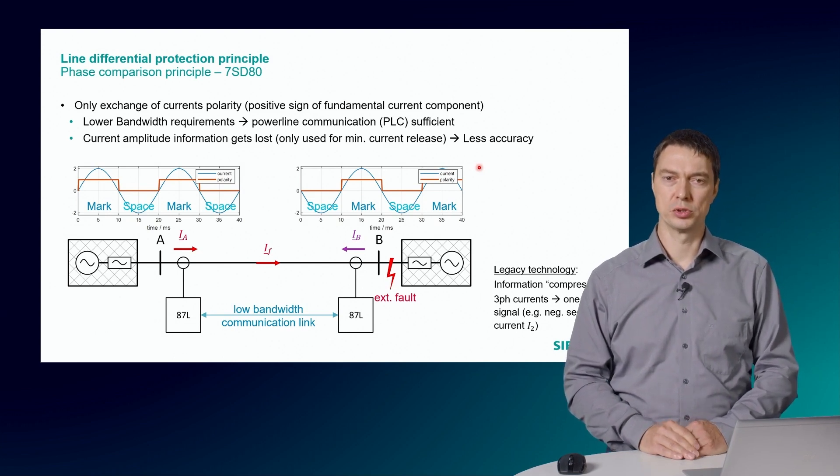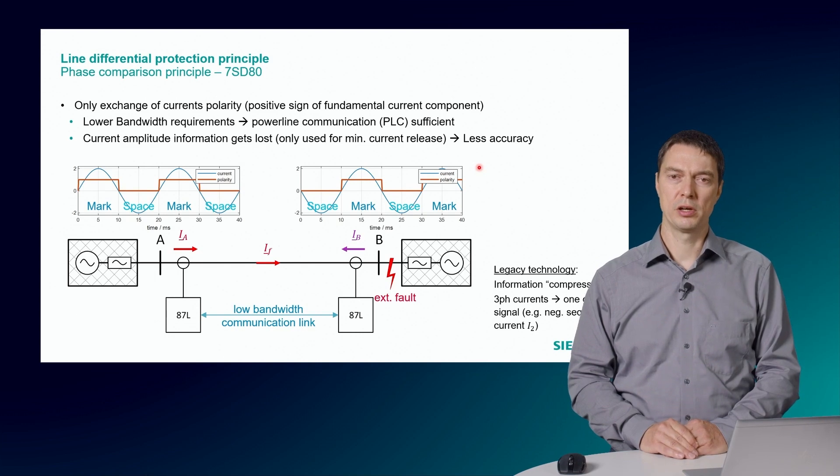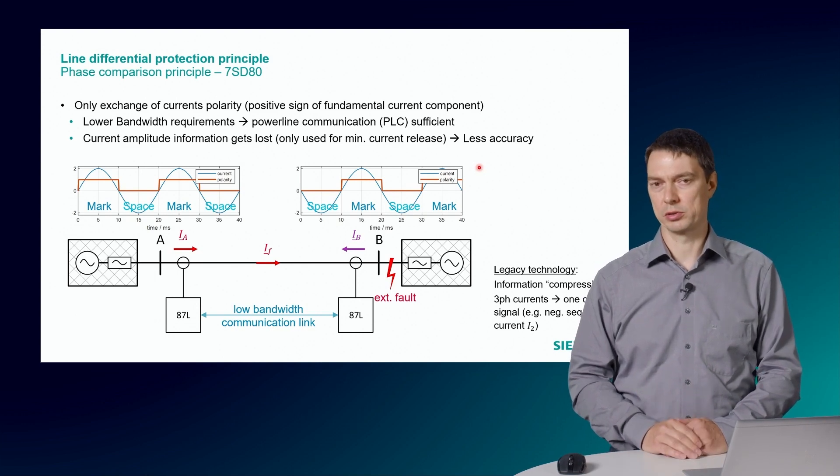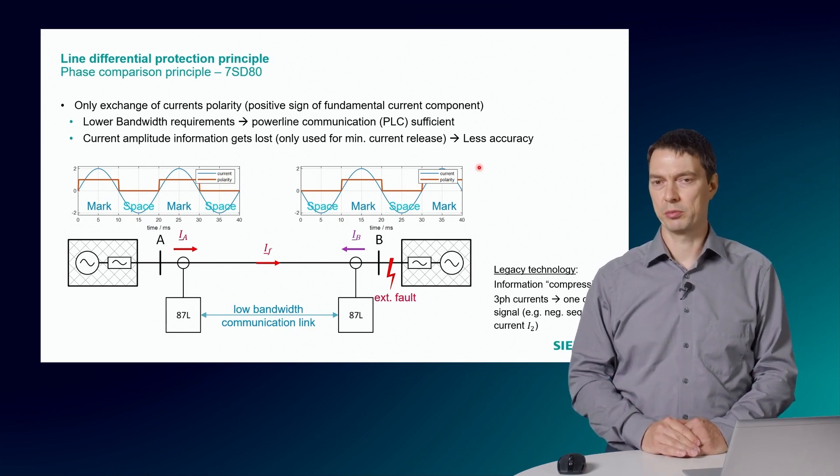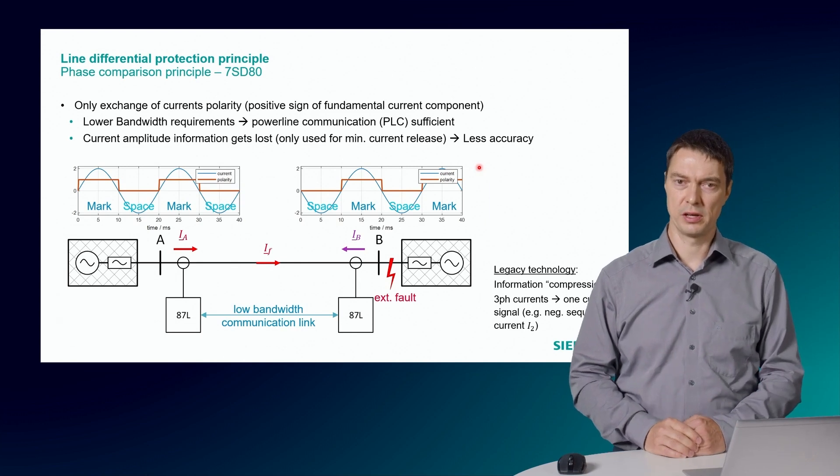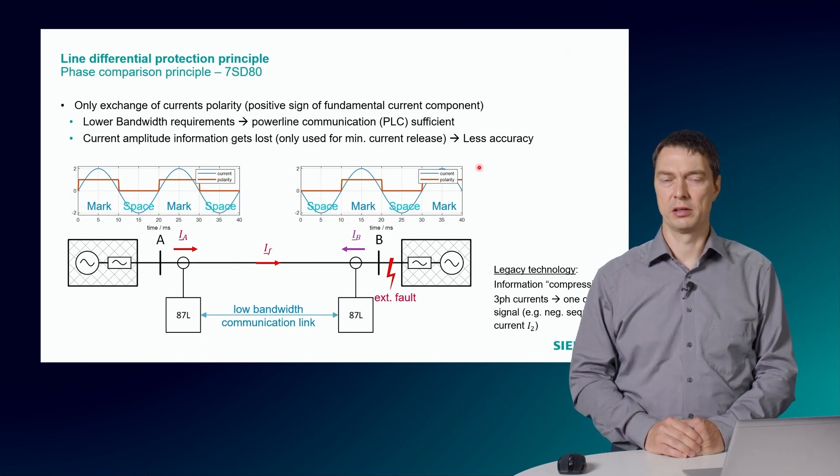The lower bandwidth requirements allow also that a power line communication system can be applied for this protection principle. The current amplitude is evaluated only for a release threshold. Therefore, some information is lost and this principle is less sensitive and accurate than a current differential protection.